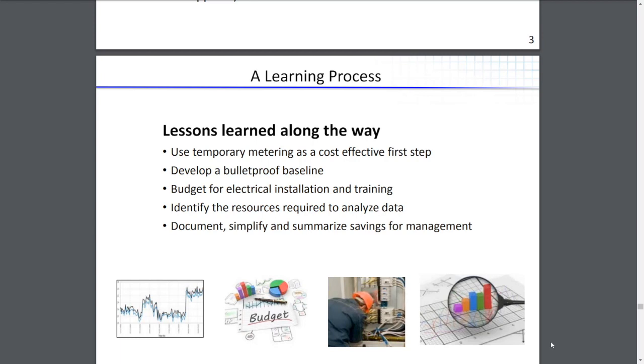Electrical installation—I can't wait for smart meters to be installed. Right now, a typical utility meter costs $300 to $500 just to get a pulse output showing kilowatts used. That's a simple contact, which doesn't sound like much, but at a large industrial site it can require lots of wire, conduit, and electrical work. If the meter is across a field or in a utility-owned substation, you can spend a lot of money just to get a simple pulse out of it. When smart meters are available with a communication link, it'll make life a lot easier and the quality of information will be much better.